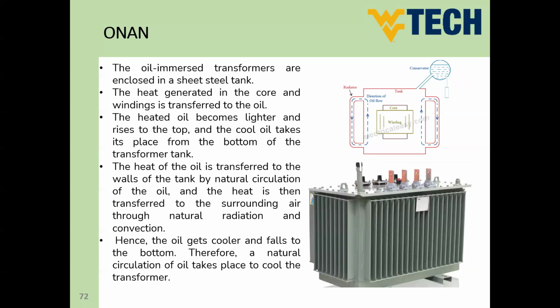What about the oil immersed one? So here is one of the oil immersed transformers. So this is the oil natural air natural. So the idea is the oil immersed transformers are enclosed in a sheet steel tank. So we have a sheet steel tank, and this sheet steel tank includes the oil inside the transformer. The heat generated in the core and windings is transferred to the oil. So once you have the transformer working, the heat will start being transferred from the winding and core to the oil. The heated oil becomes lighter and rises to the top, and the cool oil takes its place from the bottom of the transformer tank. So this is the kind of circulation that will happen in the radiators.